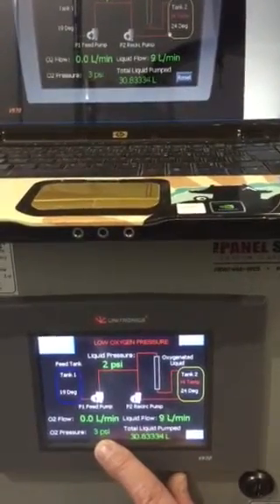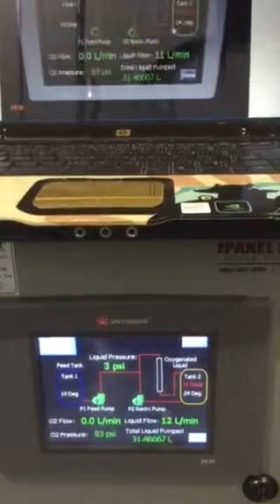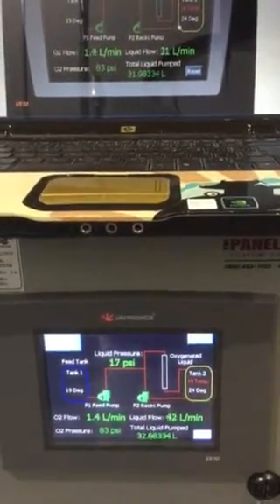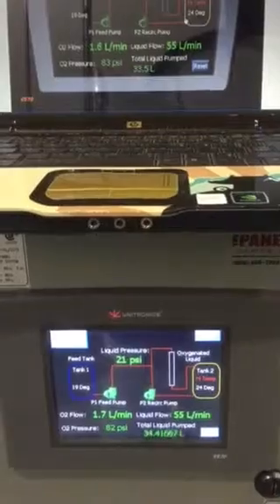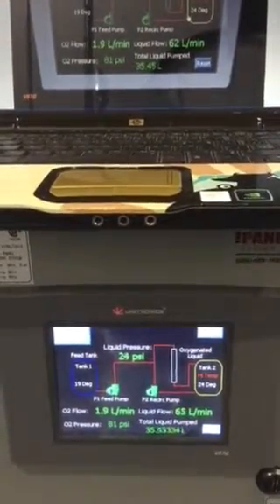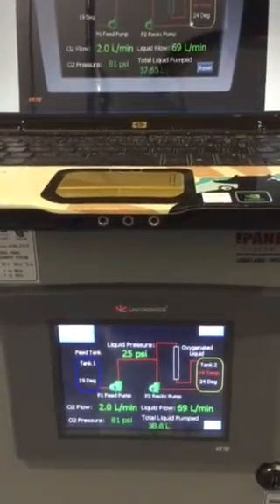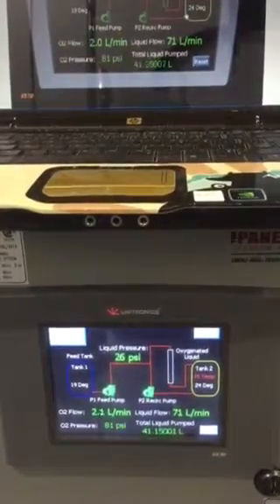If I let the pressure back up, it goes up to 80 pounds again. Should run it around 80, 85 pounds. It'll be good. As long as it's more than 60, it won't shut off. So everything's back and operating again automatically.